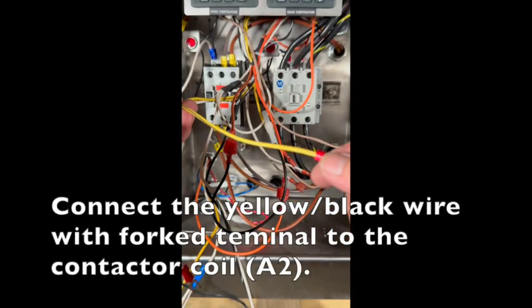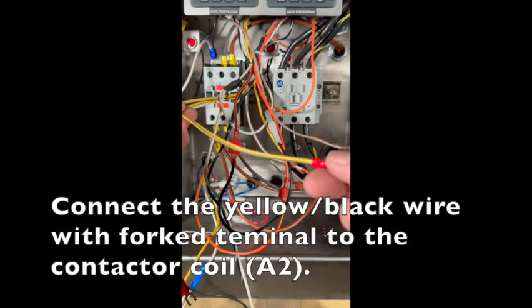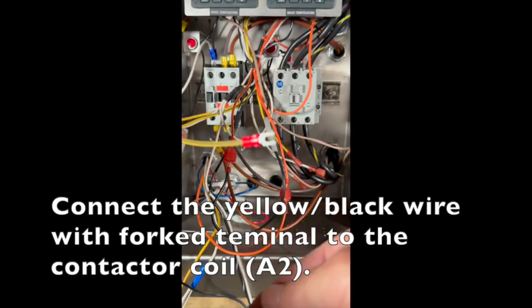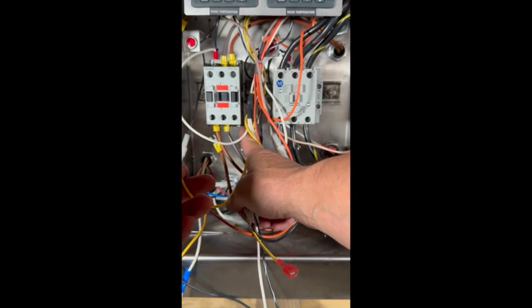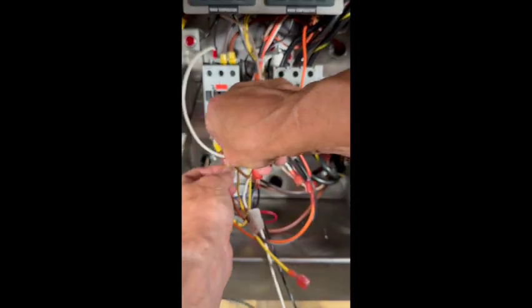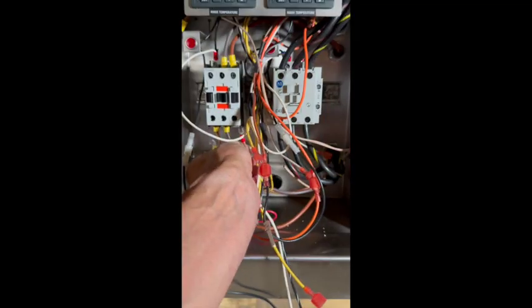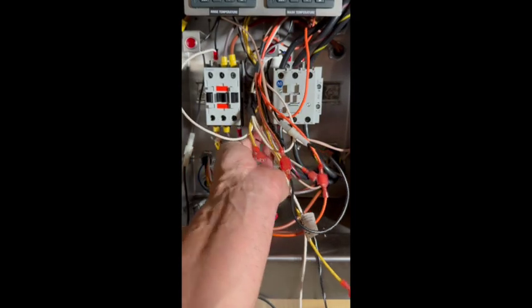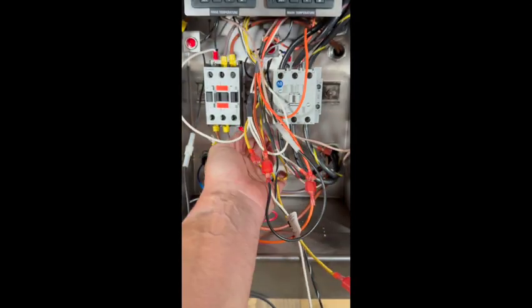Going to find the yellow with black stripe. And again, it's going to have that forked contactor terminal on it, and that's going to go on A2. Now on the 30 amp contactor, the A2 connection is at the bottom.